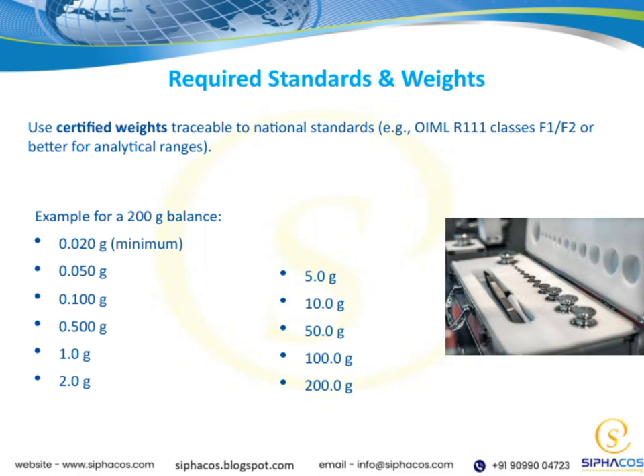These smaller weights are crucial because they help verify the balance's precision at different points across its capacity. The main takeaway here is that using certified, traceable weights helps assure that your measurements are accurate and reliable. It's not just about having weights, but about having the right ones, certified and suitable for your specific analytical range. This approach ultimately supports the integrity of your measurements and compliance with standards.